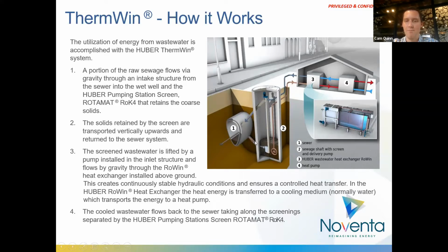But what we do is that pipe is connected to the Huber ROK4, and this is a screening device. So as we mentioned, the first challenge was the solids and pumping the solids and the impact on the sump pump. So what this screening device consists of, and I'll show pictures on the next slide, is it has a 5 millimeter perforated basket on the bottom. So all of the sewer water entering the wet well needs to flow through this 5 millimeter perforated screen before it gets to the pump, which obviously anything greater than 5 millimeters gets stuck in the screen.